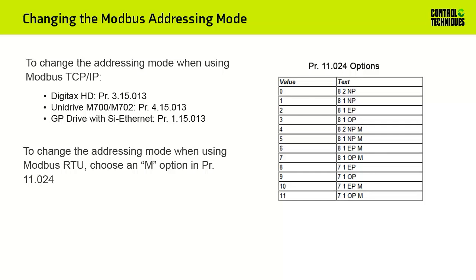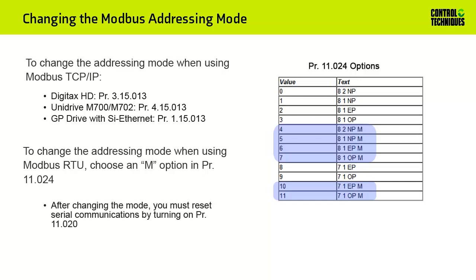The settings that include an M in them, such as values 4 through 7, 10, and 11, are what you would choose to change the mode from Standard to Modified addressing mode. The actual value you choose will depend upon the serial communication requirements for your PLC or HMI. After changing the mode, you must reset serial communications by turning on menu 11, parameter number 20. This parameter will turn off by itself once it's turned on.